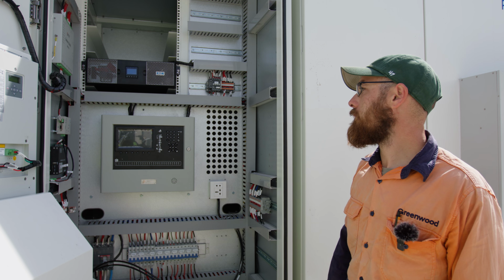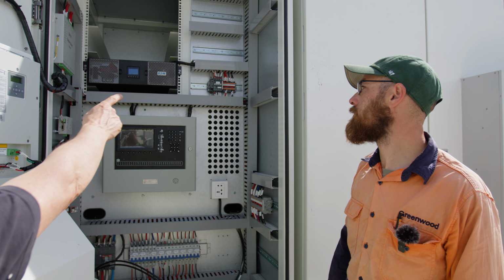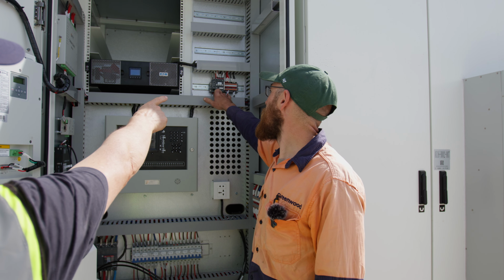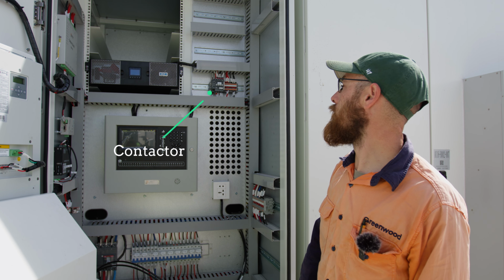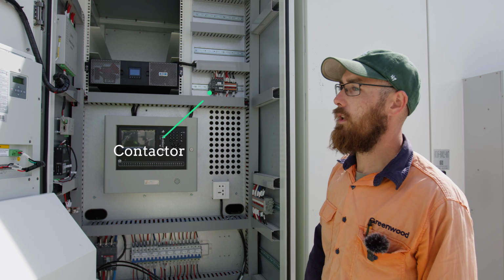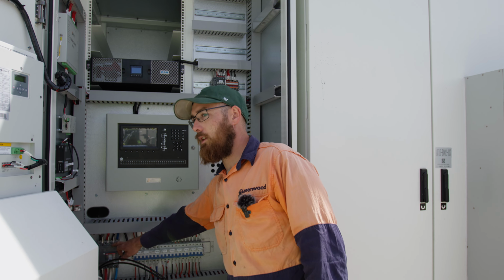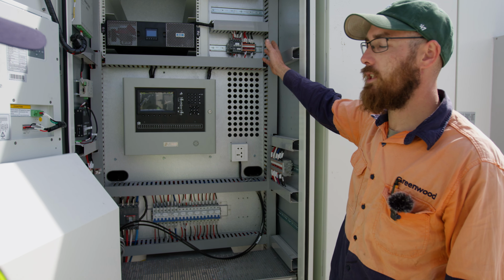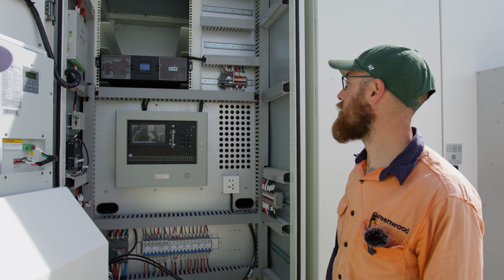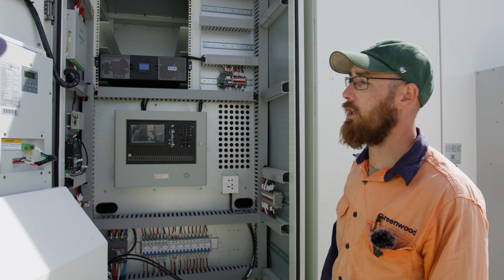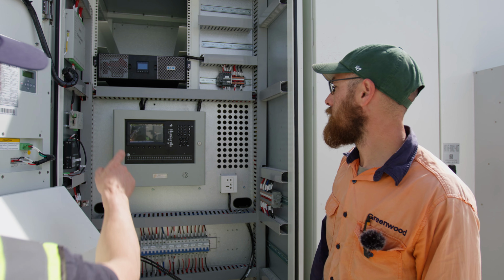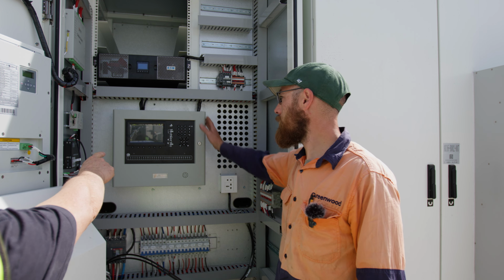What about over here, over this section here? This is a contactor. It is for the UPS so that it will switch between grid supply, which is fed from down here, or disconnect that in a UPS situation. Just for safety measures, they put that in.